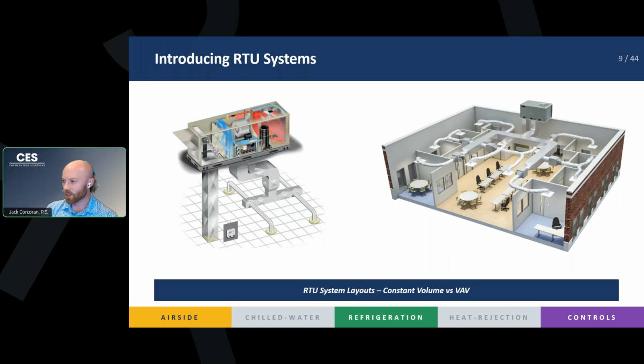Each one of these zones is going to be able to be controlled independently, right? It's a VAV system. So you have VAV boxes that'll open and close the damper to allow more or less air, and that means you have multiple thermostats, multiple zones, and you can have different diversities here, right? But on the left side, you see there's only one thermostat, and it looks like this is only distributing into one big room, right? You're only going to be able to dump a certain amount of air into the space with this constant volume system on the left.